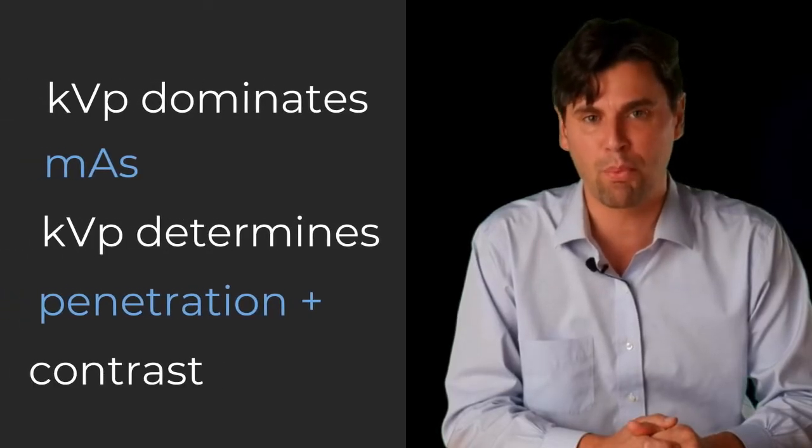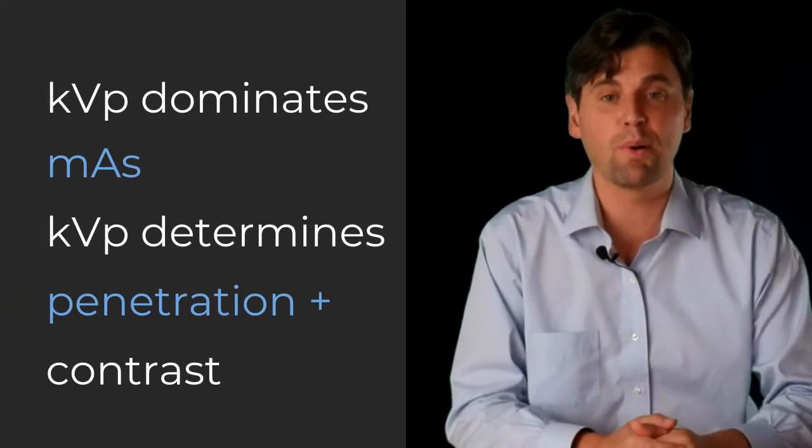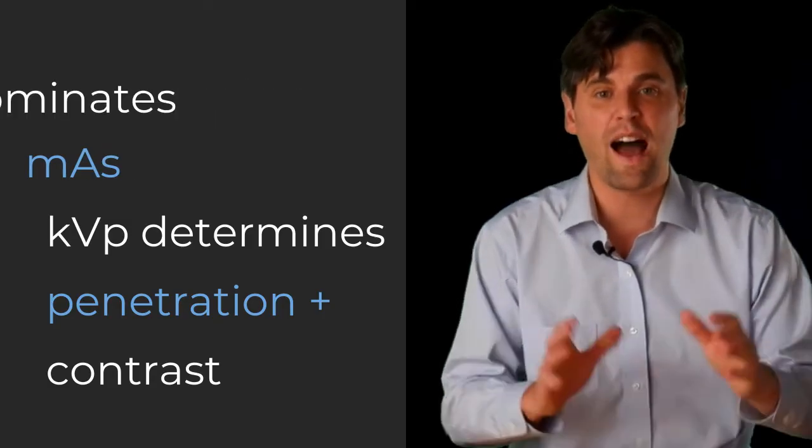KVP is very important and plays a much bigger role than the MA. So changes in KVP are much more important than changes in MA for both the contrast penetration standpoint, but also from the standpoint of how many x-rays are going to be generated. Imagine you decrease your KVP by just 15%.